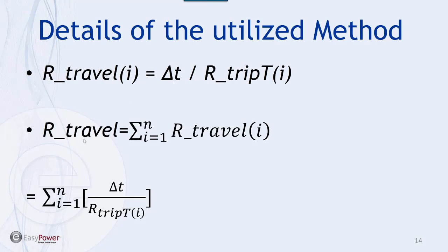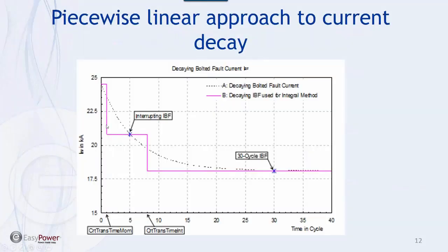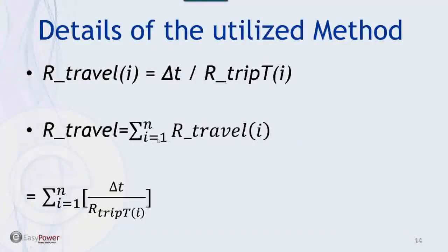So eventually, with the addition of all these values, whenever it reaches 1 or passes 1, that's when that device trips. So if we go through all this iteration one by one, we change the currents as we go from this area to here, based on these threshold values, and then we add them up.